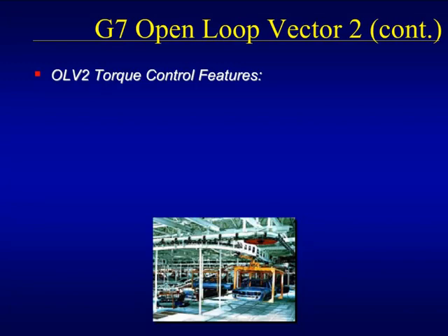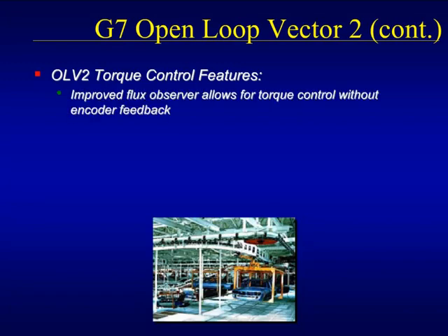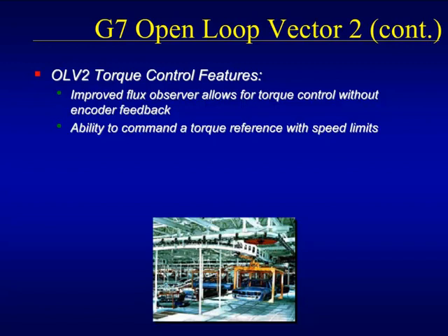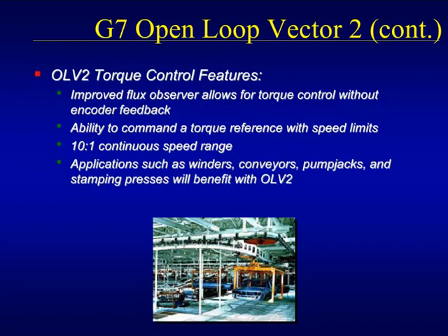Another benefit of the improved flux observer used by the open-loop vector 2 mode is the ability to perform torque regulation without feedback. The open-loop vector 2 mode will accept an external torque reference and a speed limit input to perform torque regulation over the 6 to 60 Hz speed range. Various applications will benefit from using the open-loop torque regulation without the need for the extra costs associated with supplying motor feedback equipment.